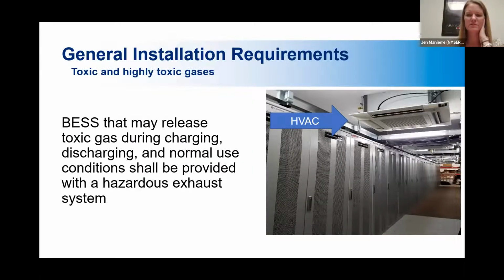Some more examples of some of those safety features that are included in the code. Alluded to it a little bit, but if you have an energy storage system that might release toxic gas during charging, discharging, and normal use, they need to have a hazardous exhaust system. As it turns out, lithium ion batteries are not one of those types of batteries. They don't off gas during the normal charging and discharging. They only off gas if something goes wrong. So this is one of those parts of the code that would not apply to lithium ion batteries.